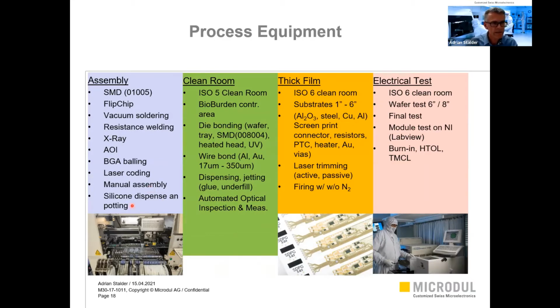Also silicon dispensing. On the next area here, we have the clean room. It's very important for open devices, bare dies. We do the die attach and wire bonding, aluminum and gold. We have dispensing, and now we can also do jetting. We can use it for glue to cover or stick components, or for underfill for CSP components. And we have some automatic optical inspection to measure the position. We also have a bioburden room for active implants, to have no bacteria outside of the titanium housing. So that means they are in a very special controlled room.